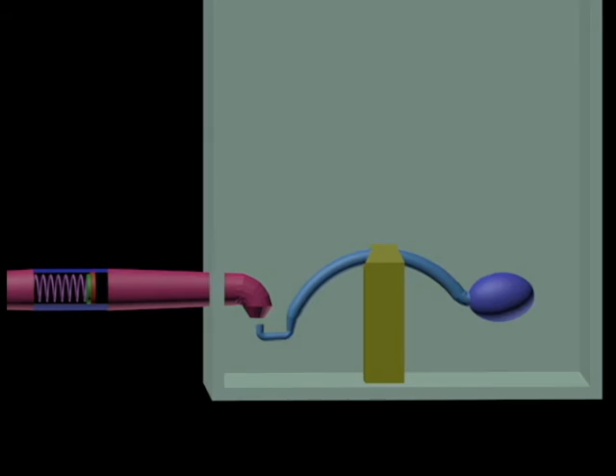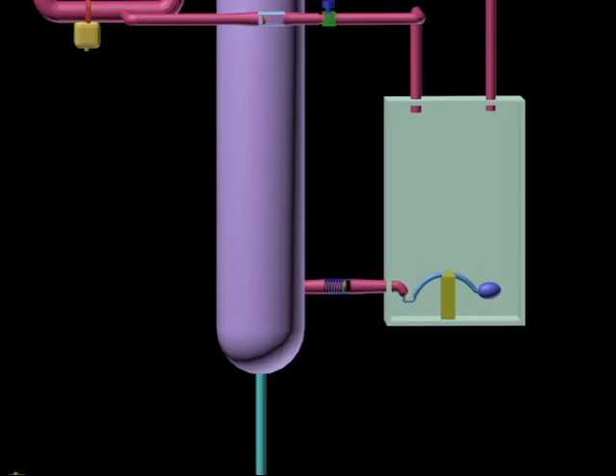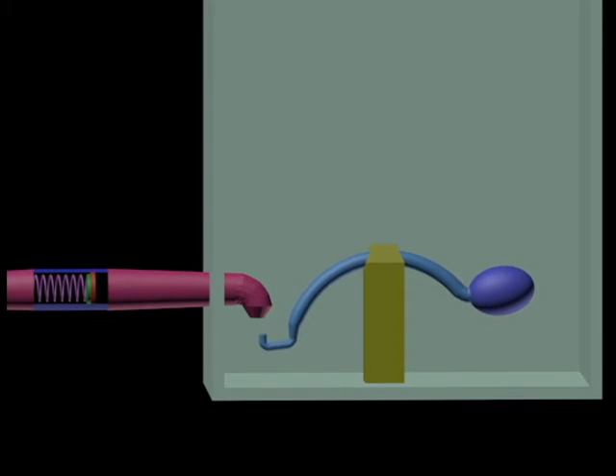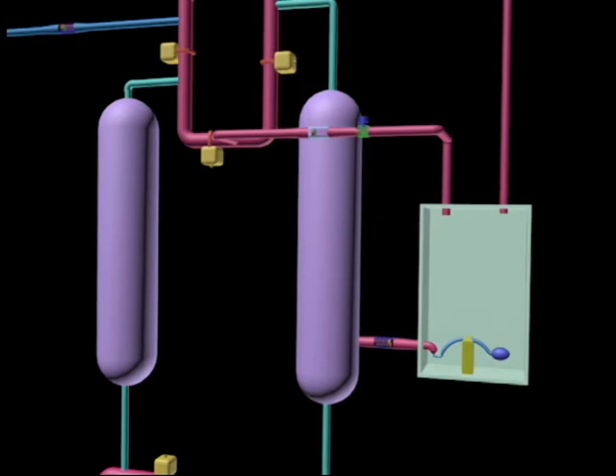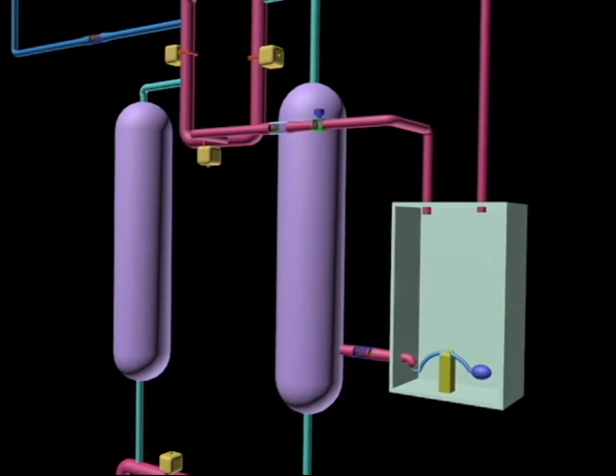The oil separator function is to send back to the tank all the liquid which accumulates in it. As the liquid rises in the oil separator, the ball will move up and open the valve so the liquid starts to return from the oil separator to the tank. There is a one-way valve between the oil separator and the tank which only allows the liquid to move in one direction, from the oil separator to the tank.